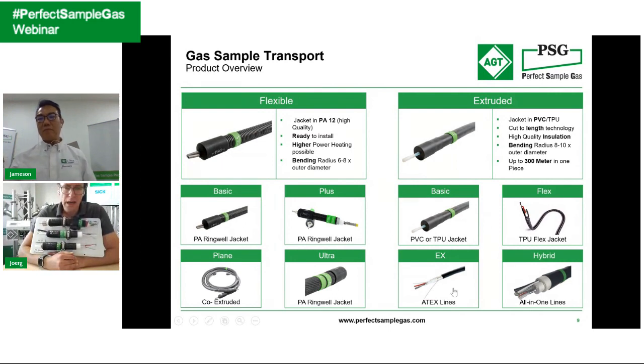It's a super high, super sensitive technology, and at the end, it comes down to condensate, which is caused by cold spots. So we cannot outline enough the importance of avoiding any condensation in your sample handling system.